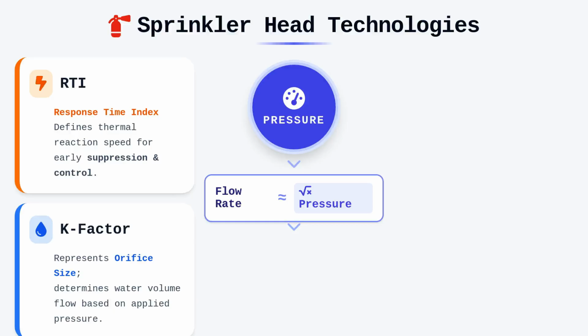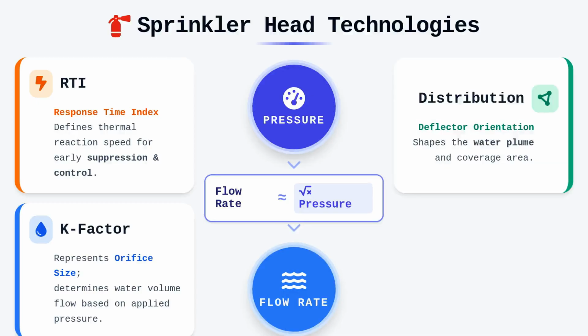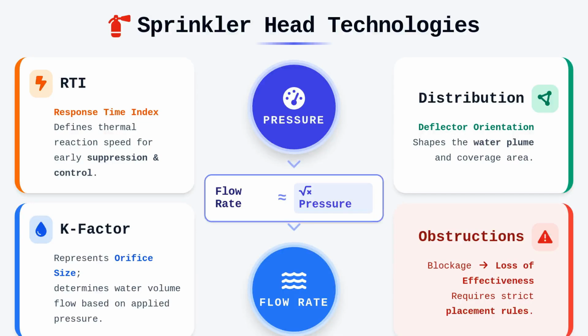You must also consider spray patterns and coverage areas, as the orientation of the deflector determines the distribution of the water plume. If an obstruction blocks the spray, the suppression effectiveness drops, necessitating specific placement rules for how close a sprinkler can be to walls, partitions, or structural elements.